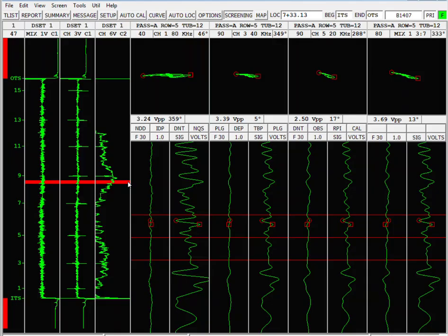of dead data spots. Now, in eddy current testing, there are a few types of tests where you don't have to be moving the probe. One good example would be doing a conductivity test. If you have a surface probe and you set it down on the test material, and then you click the button on your tester that says take measurement, the probe doesn't need to be moving. It can be a static type of test. However, when you're testing tubes with an encircling coil, or in this case, an inside bobbin coil probe, in order to find discontinuities, the probe has to be moving.